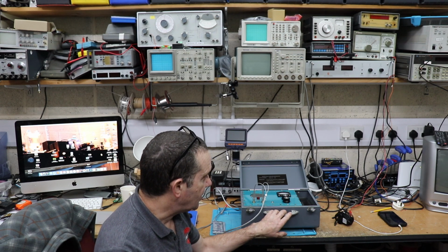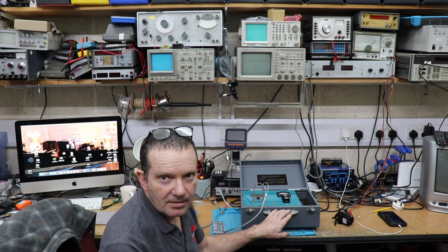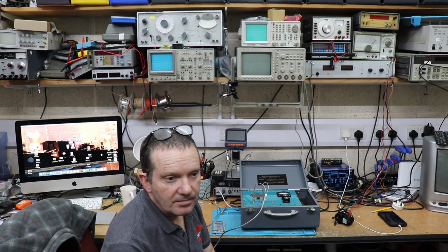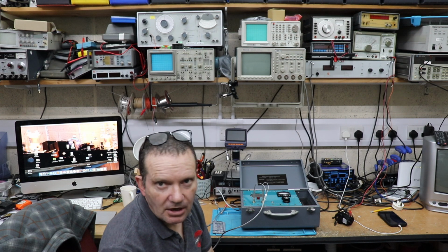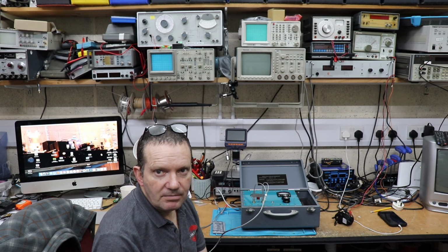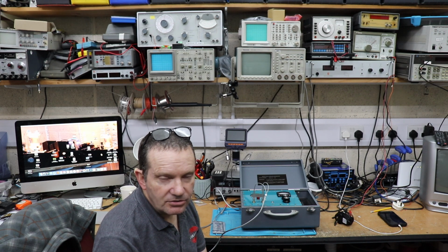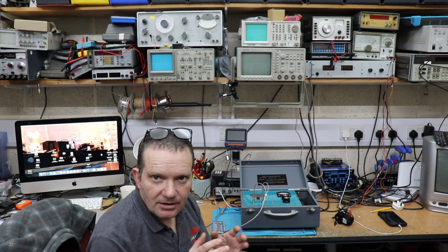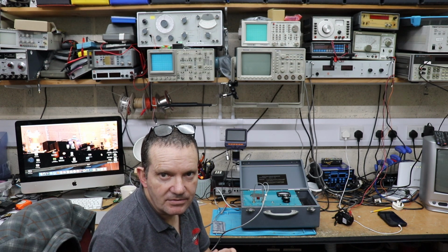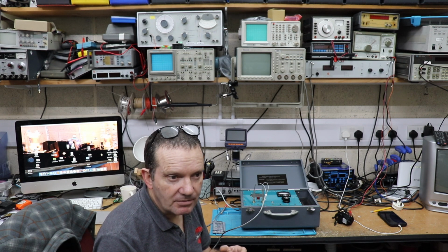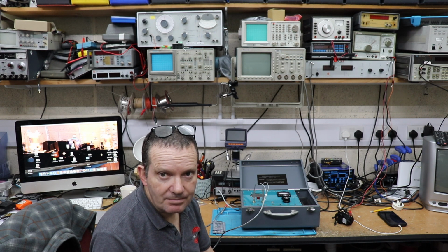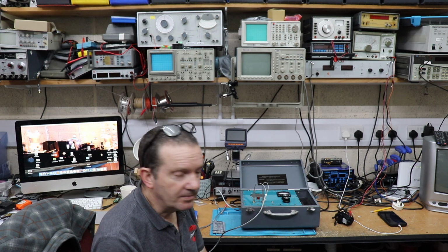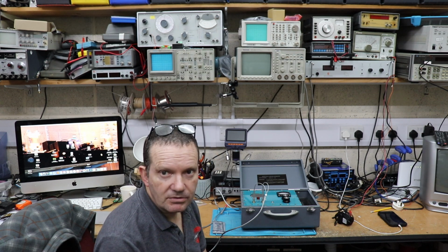And this machine basically uses some piezoelectric crystals in the probe to emit some ultrasonic waves, which are emitted, bounce back off the moving blood in the artery, or whatever vessel you're probing, and that signal is then received by the machine, or by another crystal I should say, in the probe, and then it's amplified, and then what you hear is what comes out of this particular unit, or whatever unit you're using.